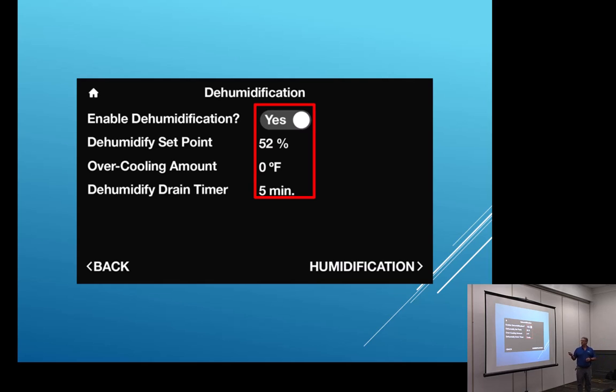It comes from the factory, if you get those guys that love to go in here and play with stuff, at 52%. Is that realistic for our market, to get 52% relative humidity in the home? Probably not. 56, 57, maybe 58, something like that. Now, if they want more or less, what do we need to be talking about? A dehumidifier. Because the air conditioner does dehumidify, but it's just a byproduct of cooling. If the air conditioner is running, it's dehumidifying, to a certain point.